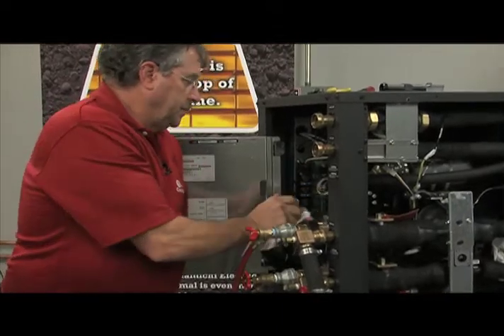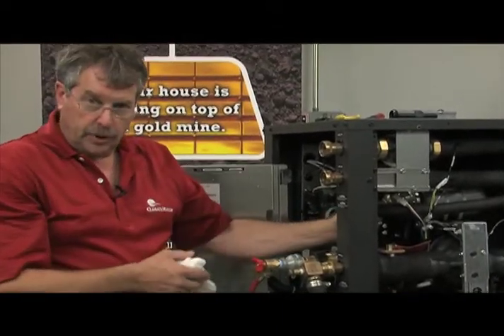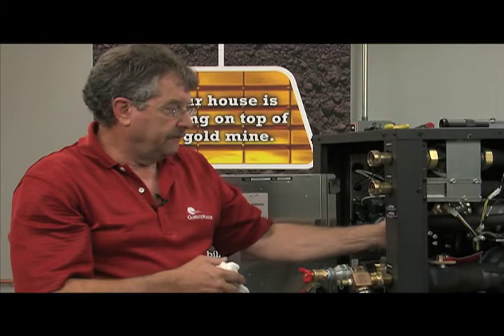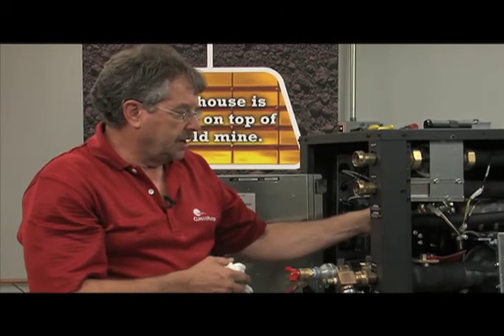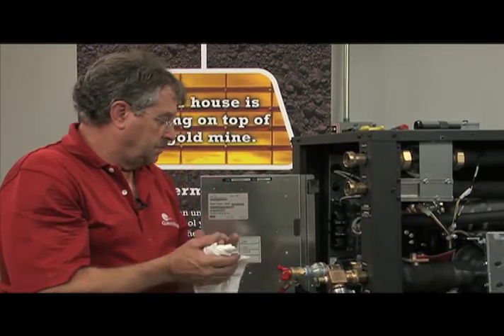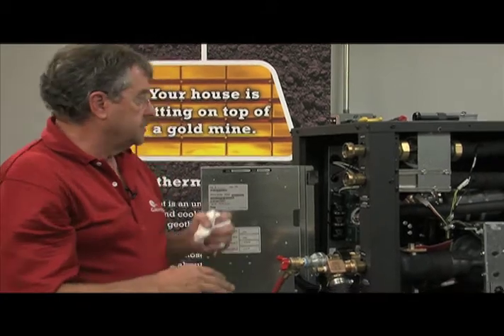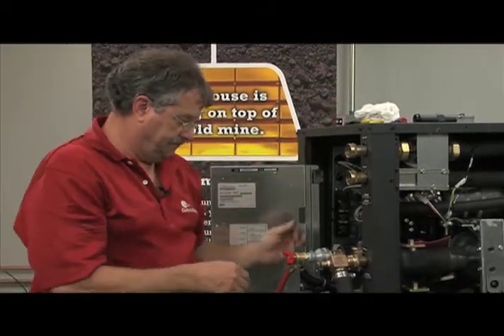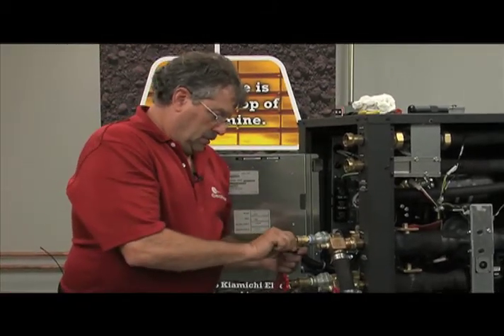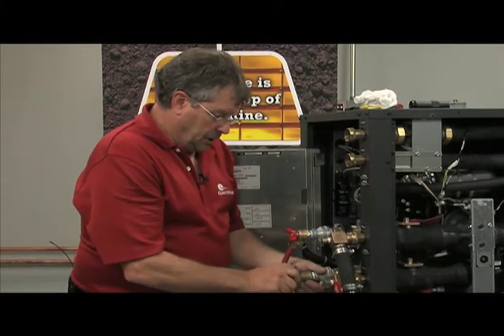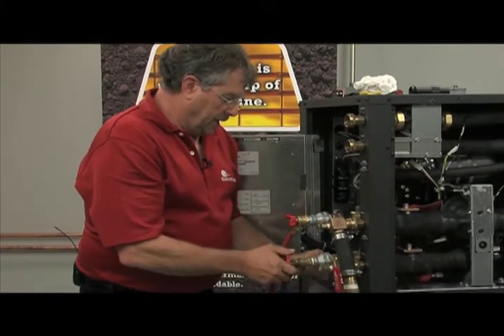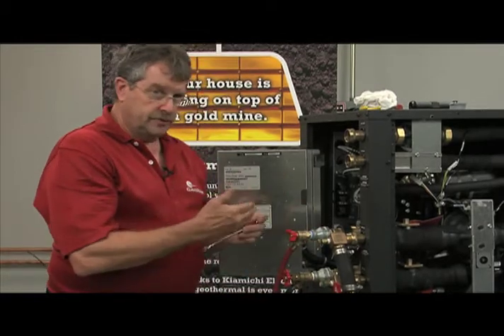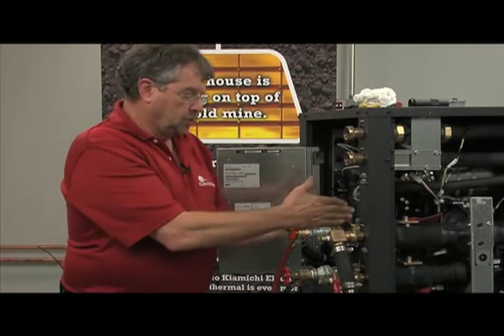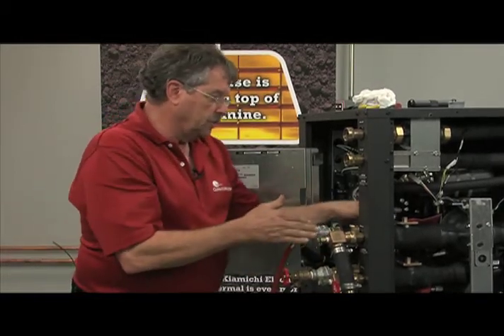Clean up the mess a little bit. Now the next step, I'm going to open the expansion tank valve and put some charge into that expansion tank against that bladder, so it gives us a little bit of drawdown capacity. So my outlet is closed. I'm going to go ahead and rotate the valves into the service position, so it'll close off here and here and open it up to the loop.